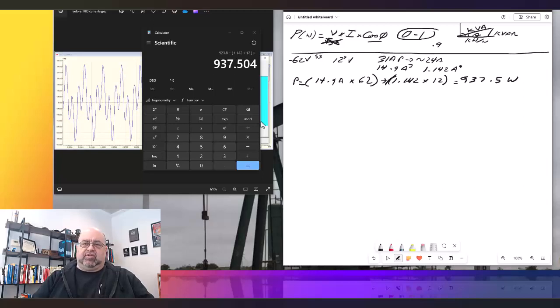Now, because this is ground, if this was on neutral, I'd still probably pick it up as part of the losses due to unbalance, and then as a result you have the current. There's a different setup for that, so we're just going to focus on that. So our direct harmonic losses are just about a kilowatt. So now let's take a look and say, okay, what are our total losses? Now this is the losses on the branch. This does not include resonance losses and all of the other losses that occur in the transformer, as well as other I2R losses in the facility, even in the conductor, right? So actually in the conductor, this is where we are, conductor and part of the ground. There are other factors that come into play as far as total losses go. So this is just a quick idea of what the losses are, but not a complete value.